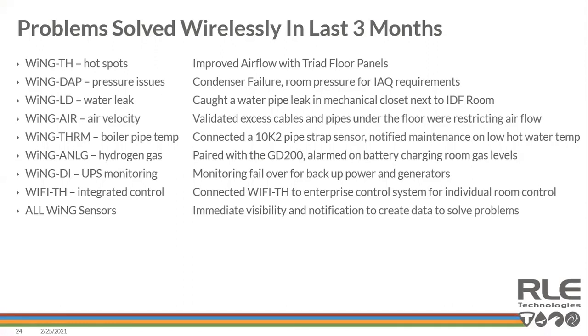Had a property manager identify that their boiler busted and went down. The pipe strap sensor on there caught a low hot water temperature, which alarmed everybody from a maintenance perspective, ultimately fixing that issue before they had residents and other people in that space throwing bricks at them.